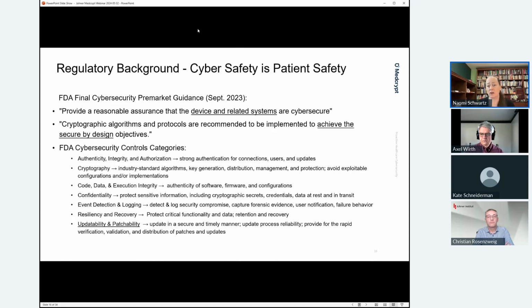And in particular, they'll be looking at all of the communication protocols that you're using. If you're citing TLS 1.0 or 1.1, they will also be asking for you to review and remove those particular types of connectivity. So it's really important to note that FDA reviewers are looking for specific keywords in your filings that they will consider to be red flags, and they will definitely raise a concern. Another area where we've seen FDA react very poorly to submissions is when manufacturers decide to roll their own crypto. And by that, I mean, somebody got the great idea that they could develop their own cryptographic algorithm. And because it's not widely used and people haven't really ever poked at it, they figured that's really secure.